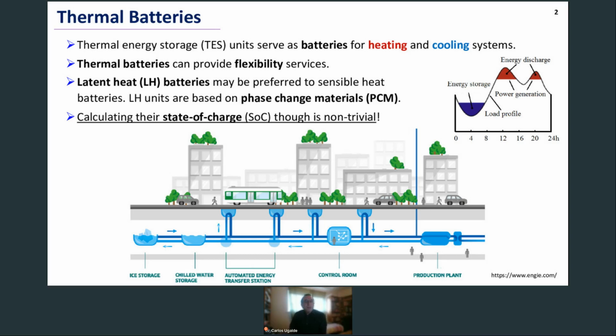Among the types of thermal batteries, those relying on sensible heat are the simplest, where the temperature of the storage medium is raised or lowered. However, in latent heat batteries, the phase of the storage medium is changed at nearly constant temperature. During the phase transition, the storage medium, called phase change material or PCM for short, absorbs or releases a large amount of heat. This is called the latent heat value.